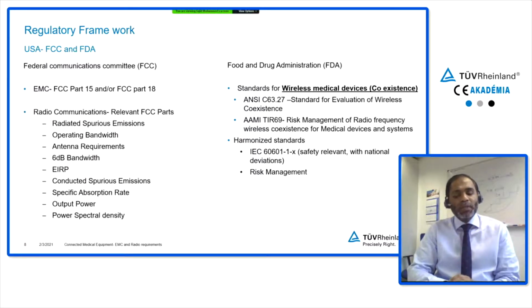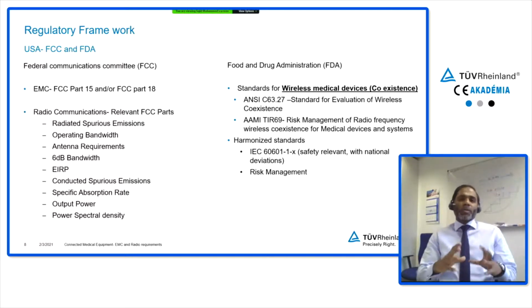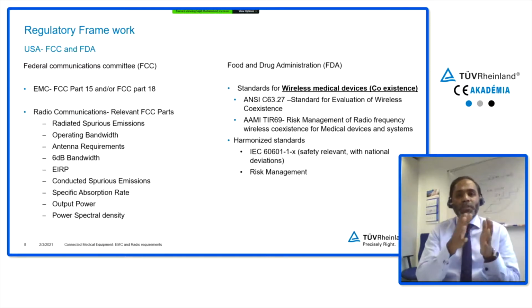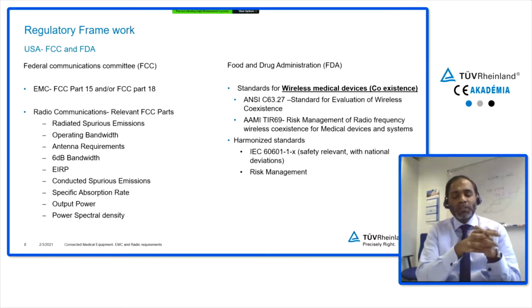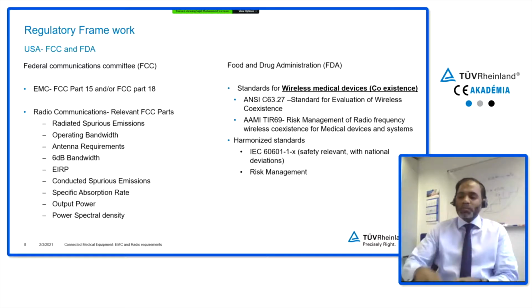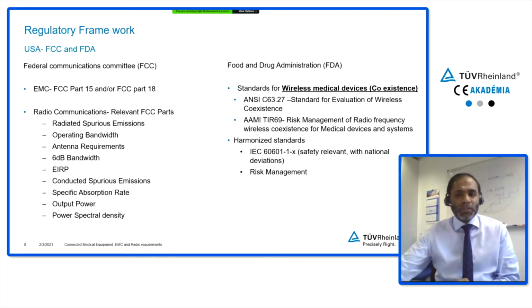More and more medical devices are being found in hospitals, in medical environments, operating in a certain area, occupying a certain spectrum, and causing interference to each other. So FDA has said coexistence testing has to be done, and these tests are carried out according to ANSI C63.27, and the risk management is given in the standard AAMI TIR 69. For the medical device itself, the harmonized standards are laid down according to IEC 60601-1-X for safety, as well as the EMC part -2, with risk management in place.